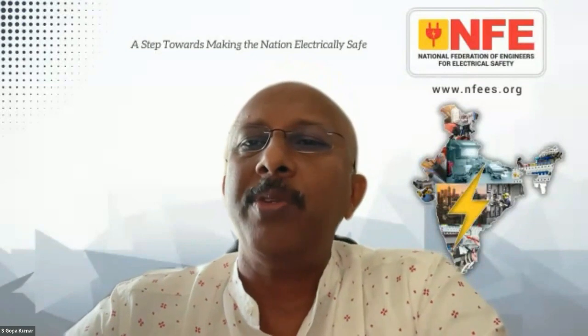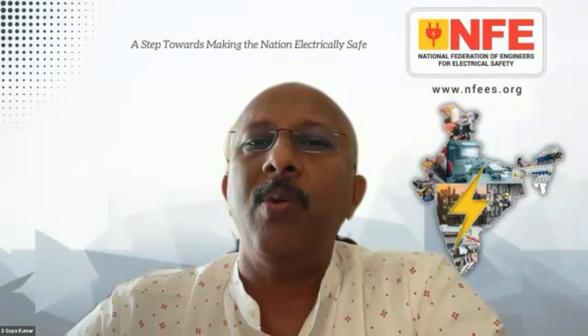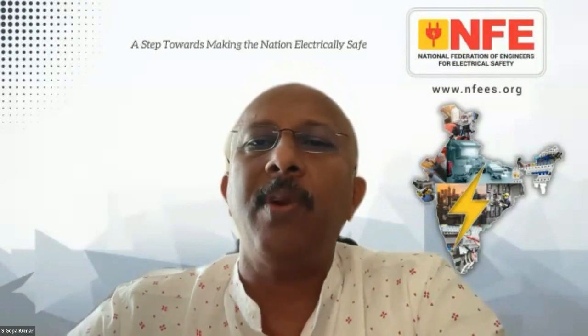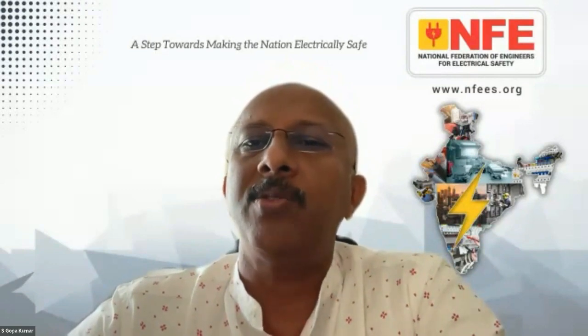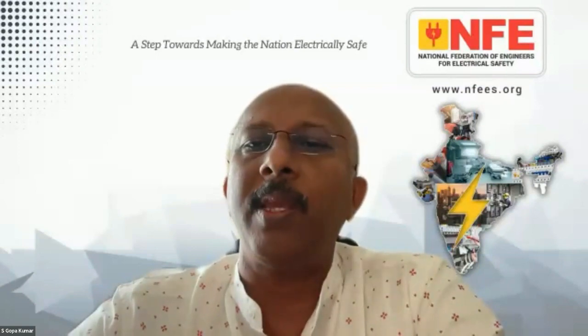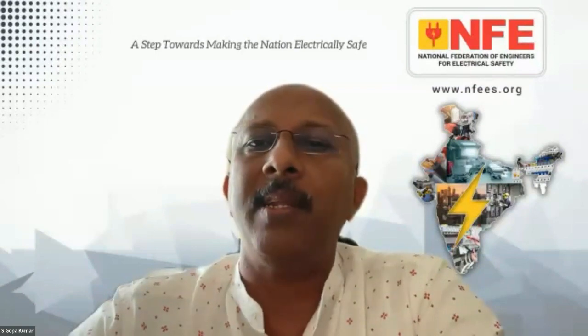So now, sir, another question. This is about solar PV. A 1200 kWp solar rooftop plant's generation inverter AC voltage is injected into the secondary of an 11 kV/500 volt transformer, with the transformer neutral kept floating. Please help to understand the reason.